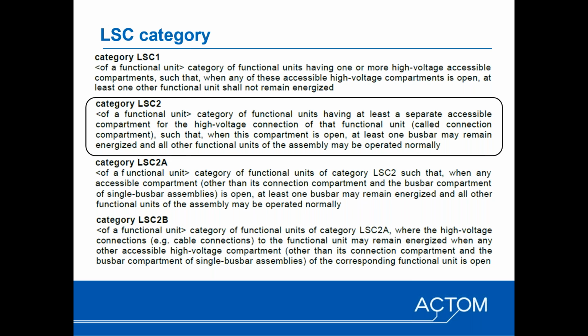In terms of fixed pattern switchgear, such as GIS or solid-dielectric insulated switchgear, SIS, there's effectively one category that's relevant and applicable, and that is LSC 2. That's primarily because the only accessible compartment is the cable connection compartment. You cannot actually get LSC 2A or 2B with fixed pattern switchgear, because the other compartments are not required to be accessed during normal use. So it's only limited to LSC 2. That's effectively a category of functional units having at least a separate accessible compartment for the high voltage connection, that is, the cable connection of that functional unit, such that when that compartment is open, at least one busbar may remain energized and all the other functional units of the assembly may be operated normally. So that provides the maximum level of service continuity possible.